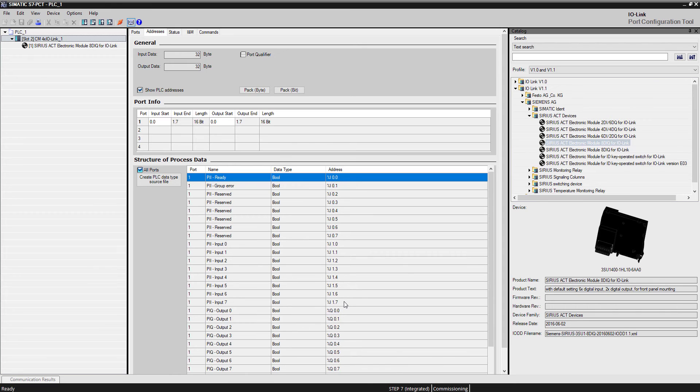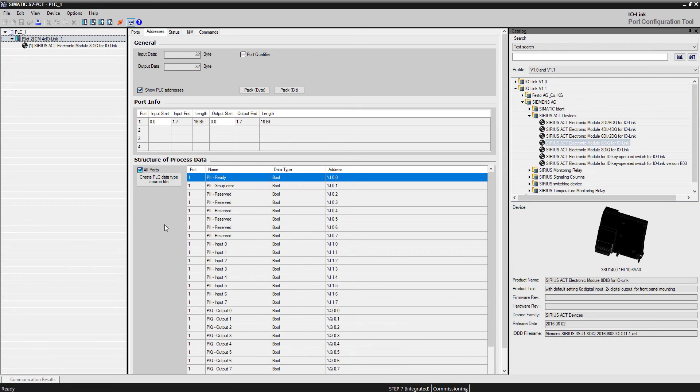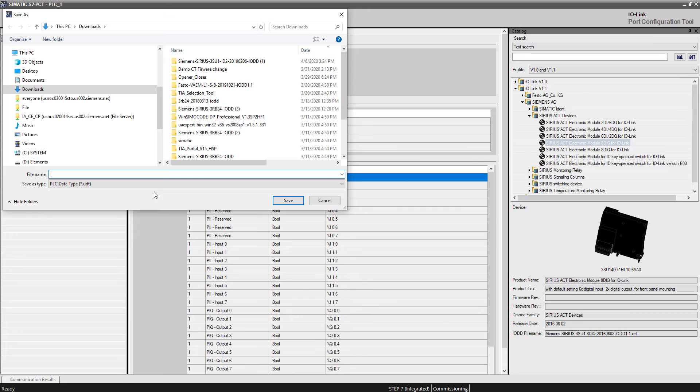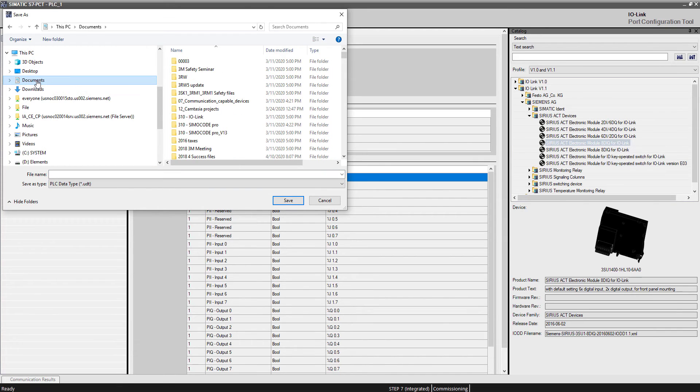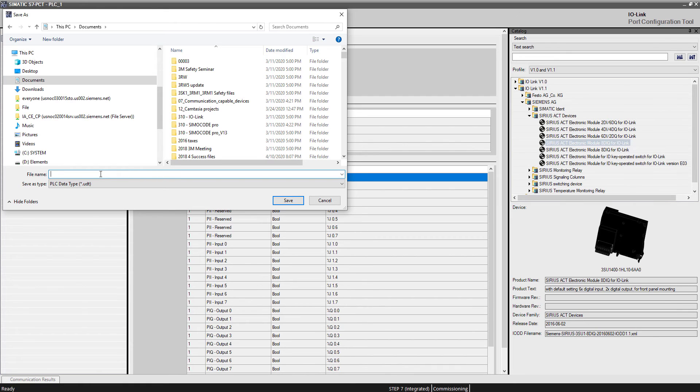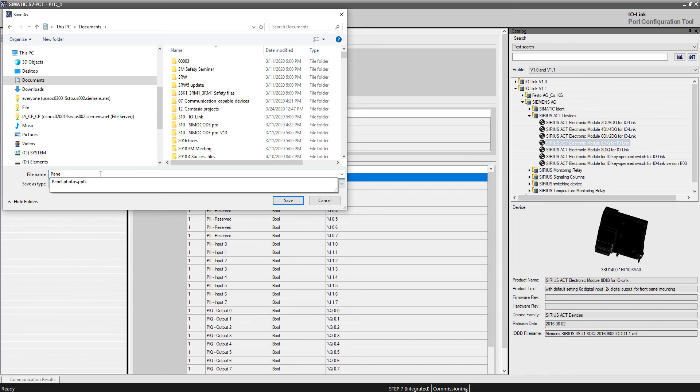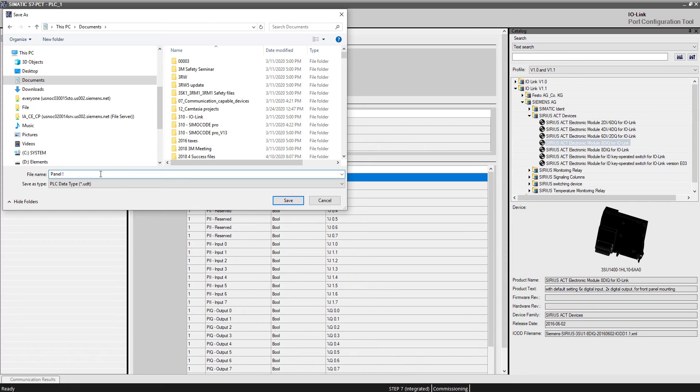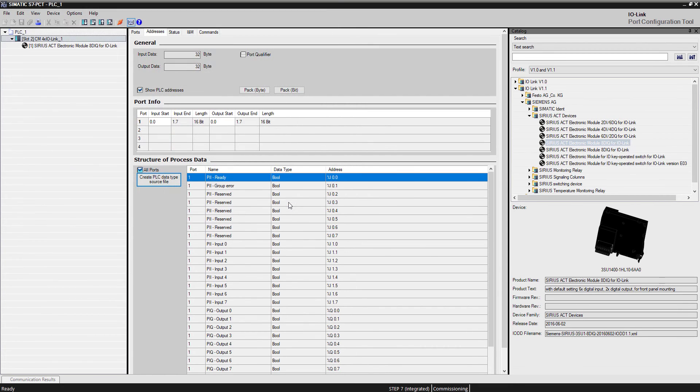So I know the addresses, but at this point, if I wanted to create PLC tags, I'd be manually creating those tags and then assigning these known addresses to them. We've actually taken it a step further and we can actually at this point create a UDT for these signals. I'm going to come in here and create a UDT. I'll put it on my folder called main documents, and I'm going to say this is my signals for panel 1. I'm saving this under documents. Go ahead and save that UDT.